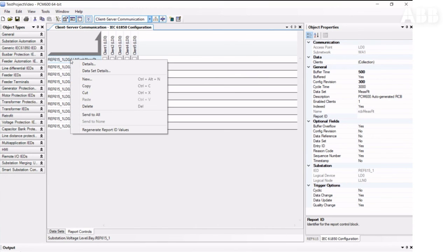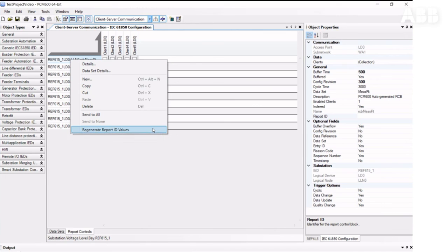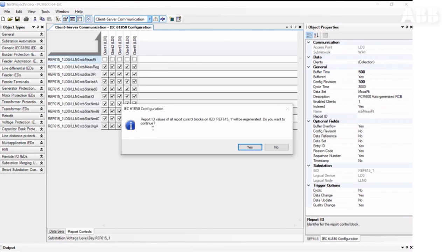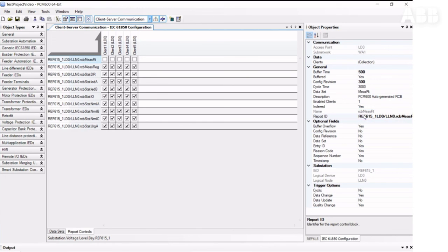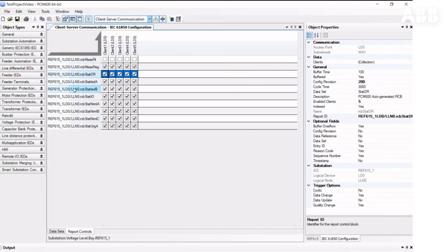To generate Report IDs, you can right-click on the Control element, select Regenerate Report ID Values, and the tool will automatically generate Report IDs for all Report Control blocks. You can look at what is in the dataset by double-clicking on it, and you can edit it if needed.